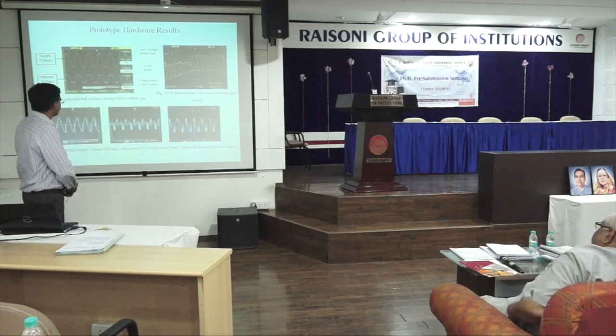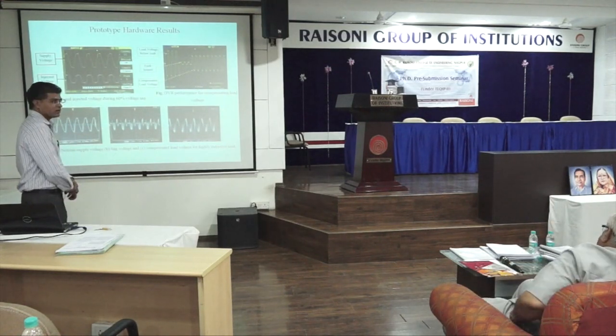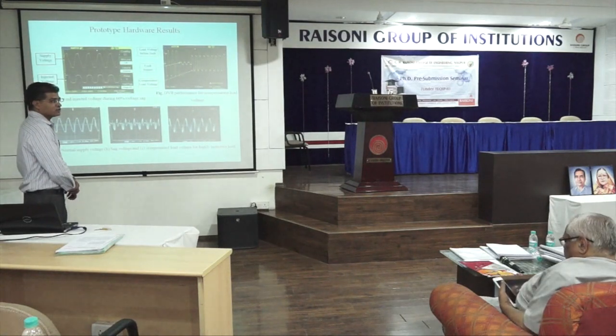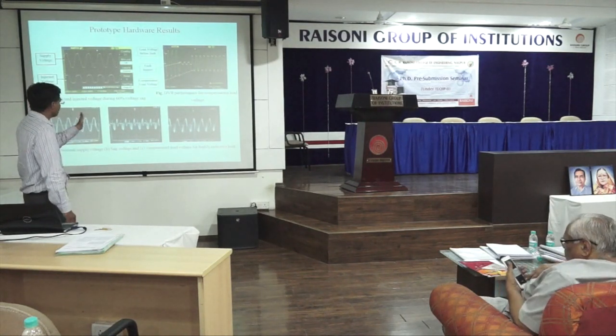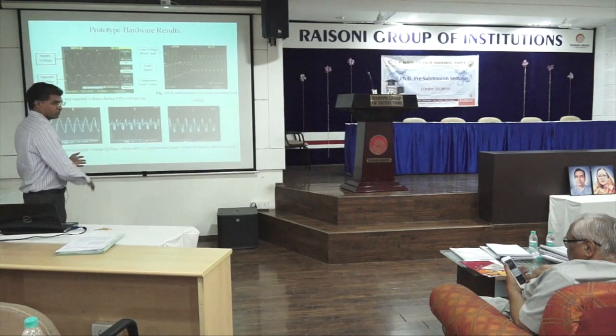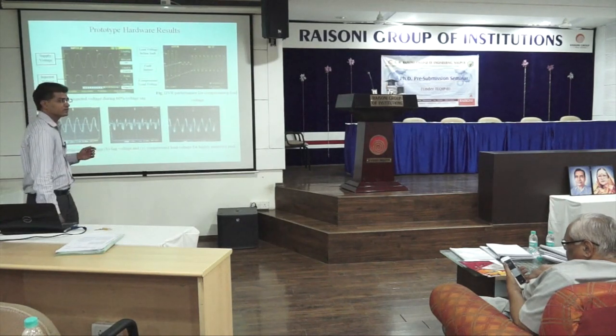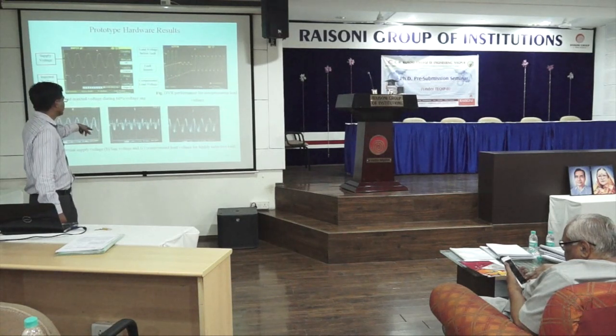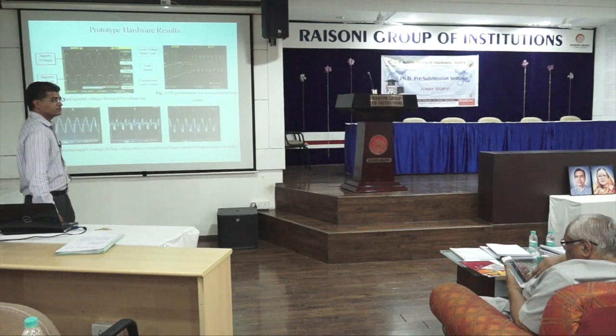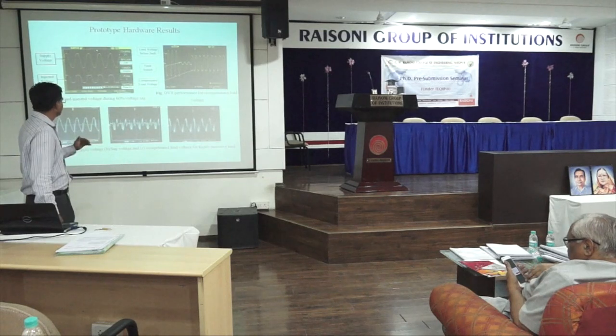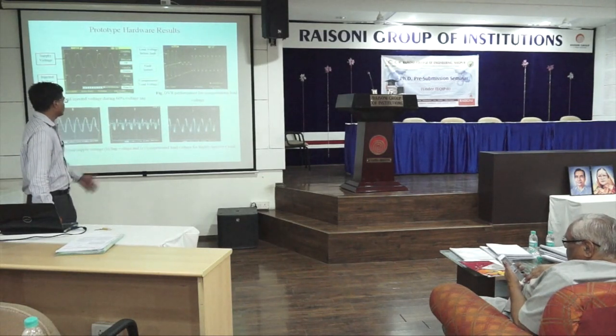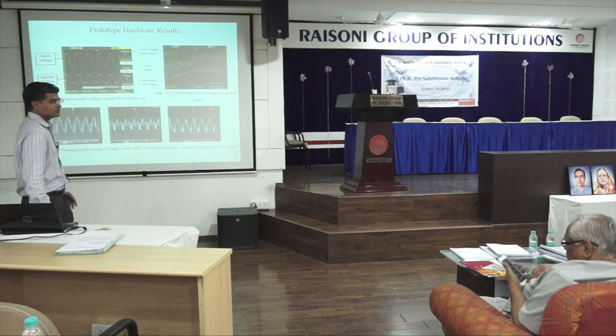This is the injected voltage. It is not showing exactly the firing angle. Due to non-linearity, the waveforms are very much distorted. The load voltage. This is the supply voltage. The middle one is the sag voltage. Sag decreasing the supply voltage. And the third one is the injected, compensated load.